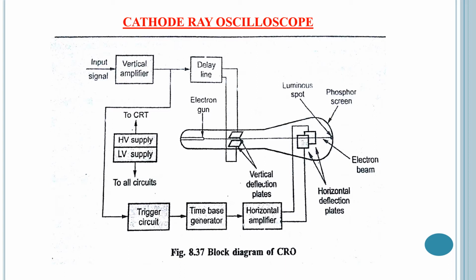In an oscilloscope, the CRT produces the electron beam, which is accelerated to a high velocity and brought to a focal point on a fluorescent screen. Thus, the screen produces a visible spot where the electron beam strikes it. By deflecting the beam across the screen in response to the electrical signal, the electrons can act as an electrical pencil of light which produces light where it strikes.